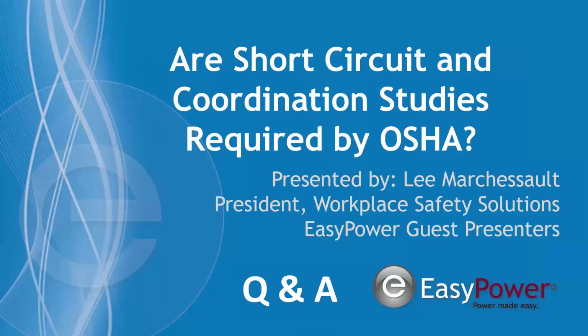Let me interject something. If I'm looking at the question right, when we're modeling, we talk about buses because the impedance has to be measured between two points, and so it's easier to measure between buses to know what the protection level needs to be to protect that particular bus. So it's in line with the cable, but it's calculated based upon what the bus voltage and current are going to see. I don't know if that helps. And the protection level of whatever's on the bus. Yeah, that sounds good.